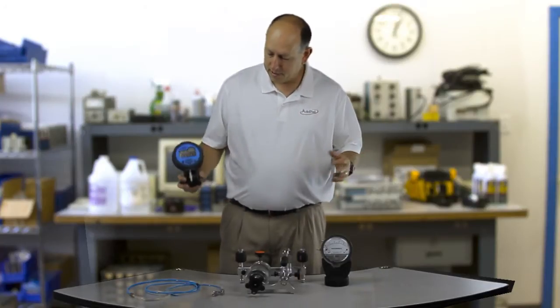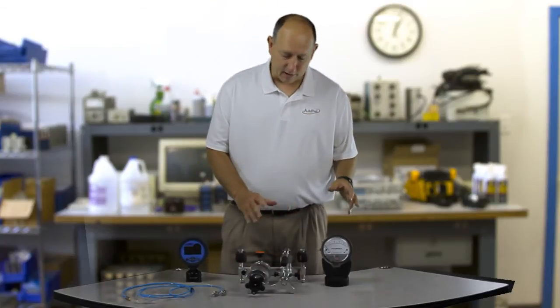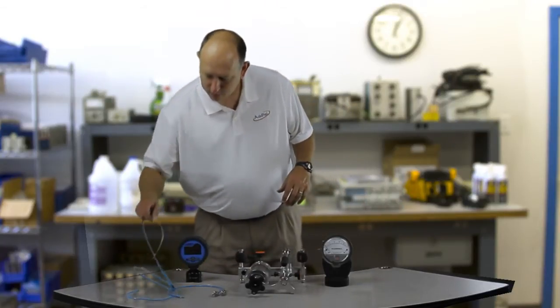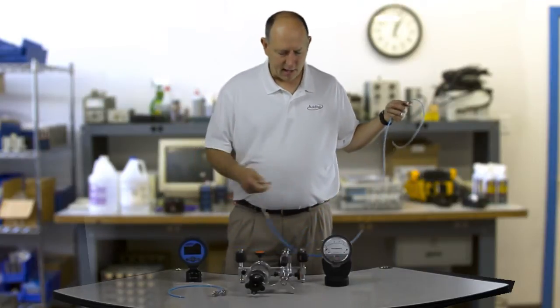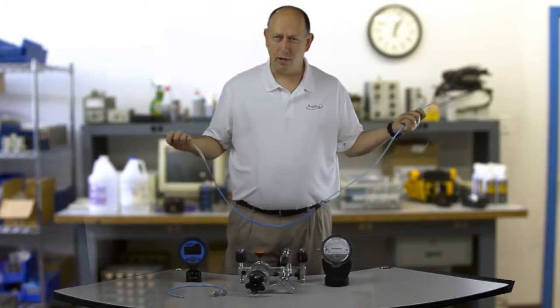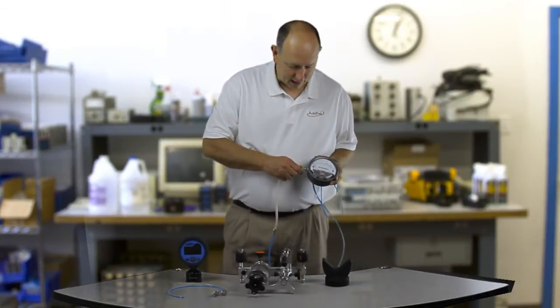These are very difficult to calibrate because it's very hard to get it stable. So how I'm going to start is I'm going to tie the low end of the reference and the unit under test together — I'm going to tie the low end sides together. So I'm going to go into the low end side of the Magnehelic here.